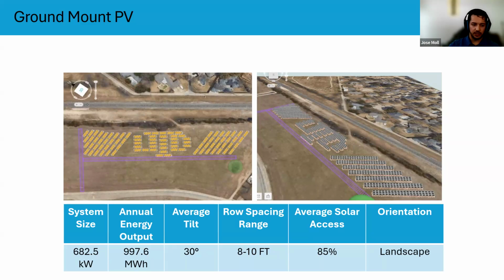One very big challenge we faced with the design was that the university had a limitation where they could not be allowed to export energy, so no net metering. The alternative we saw to creating this system while maintaining financial viability was to size our system around the noon minimum load, in such a manner that we would guarantee that at no point would we have an excess of energy production relative to the campus energy consumption.